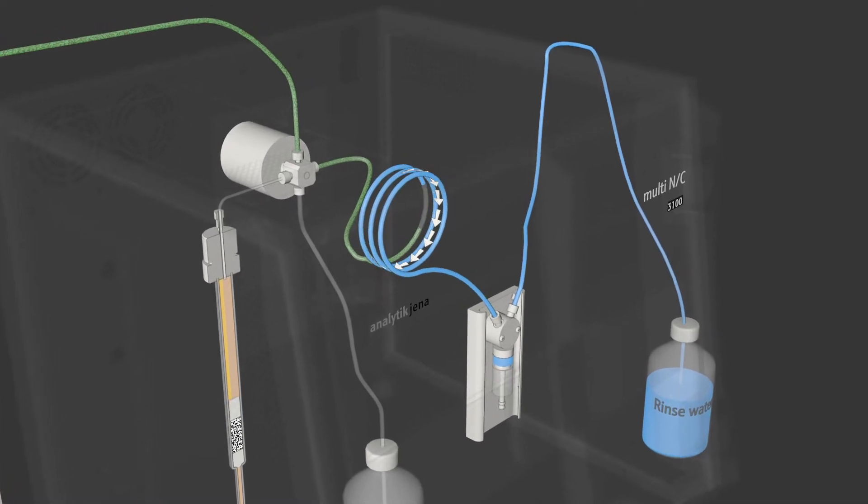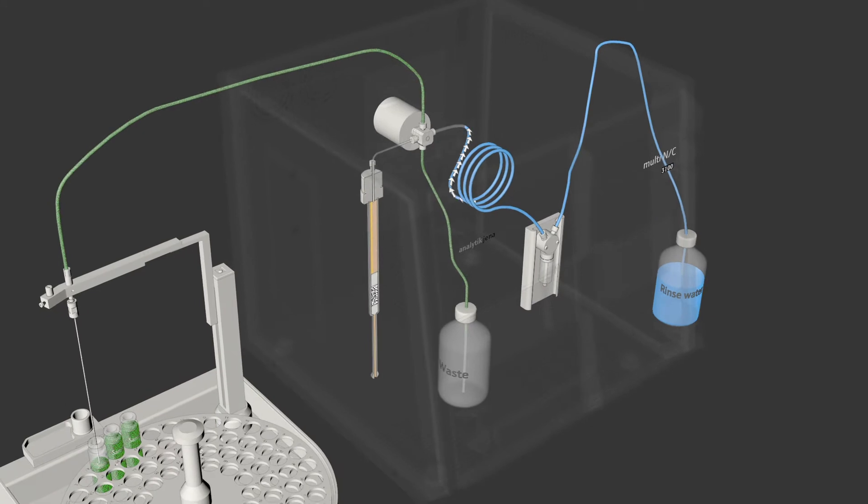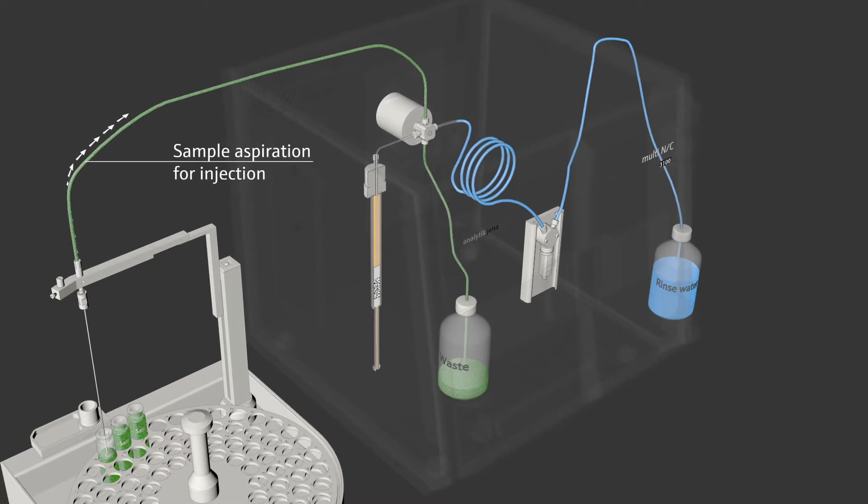When the sample is taken into the injection loop, no sample and particles enter the syringe pump. This minimizes, together with an effective rinse, carryover and material wear.